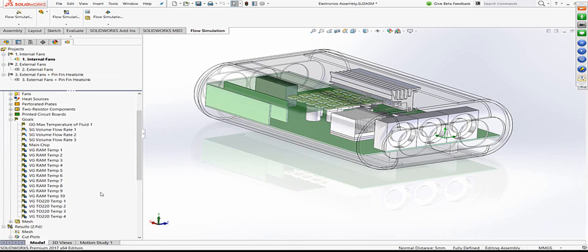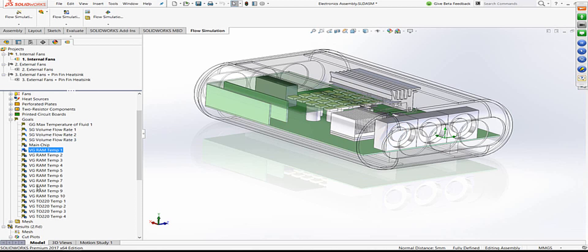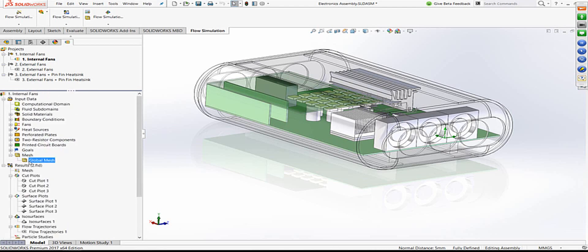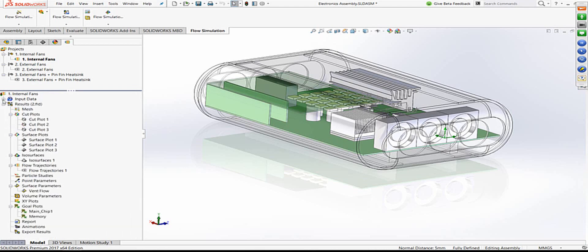The software has its own convergence logic, but we can also set goals — specific values and parameters important to us — to monitor and control convergence. We can track them in terms of both values and convergence. The goals here include temperatures of the various heat-generating components, volume flow rates at inlets and outlets, and overall system temperature. Meshing is then done; a refined mesh can be used if needed, but this completes the setup.